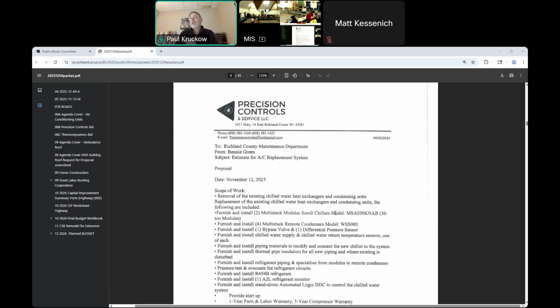We're reusing the system pumps that are already in the building, and you have redundancy on the pump side currently with your chill water pumps. So we are tying into your chilled water system. The modules would sit in the basement in the boiler room, and we would tie into the chilled water piping that's there.